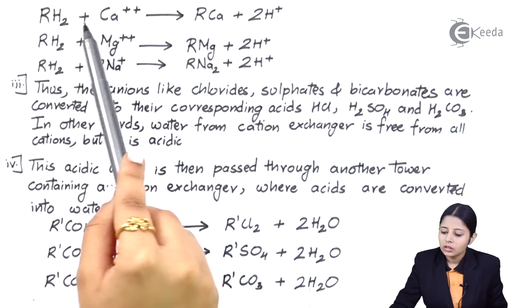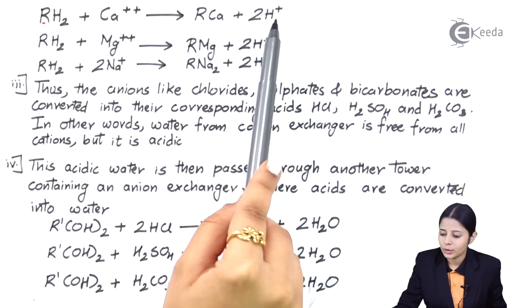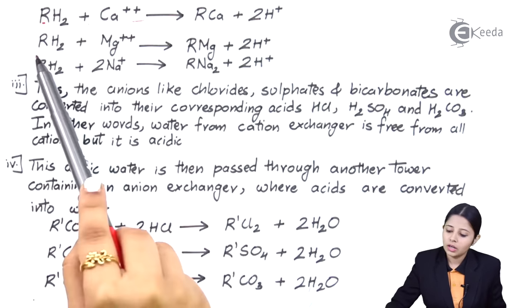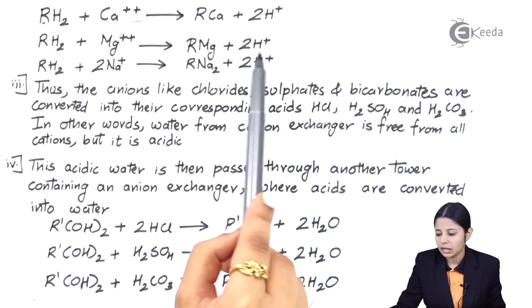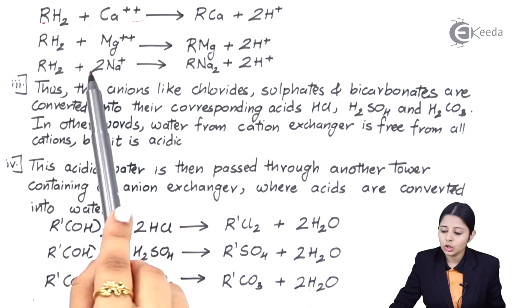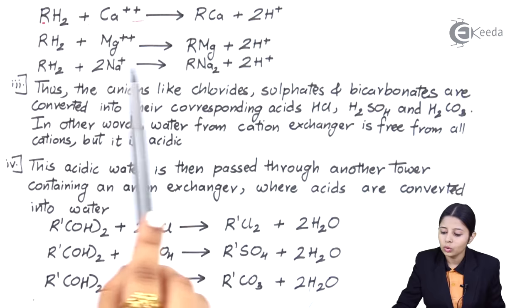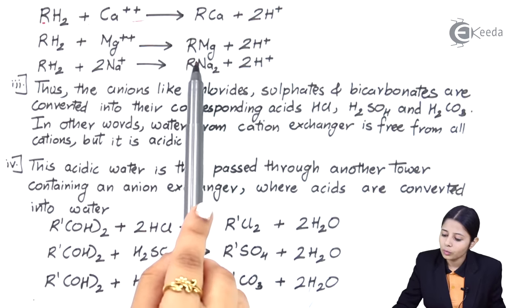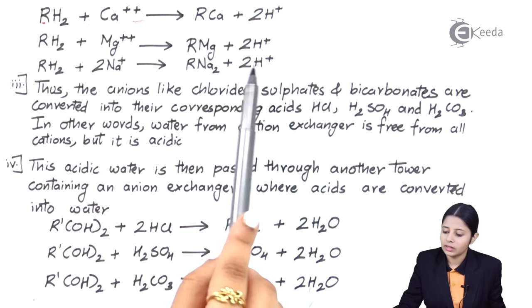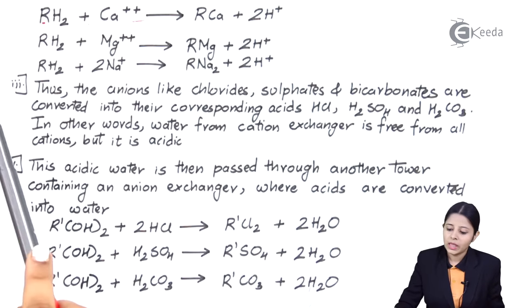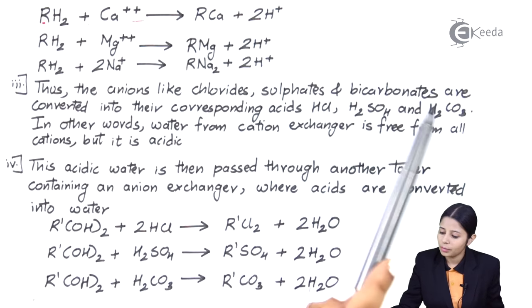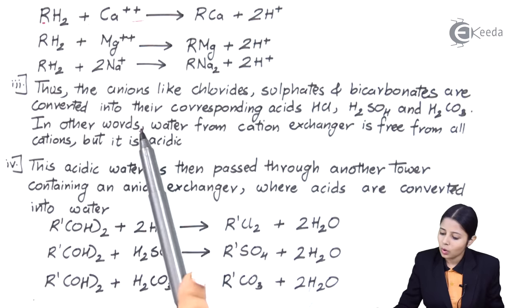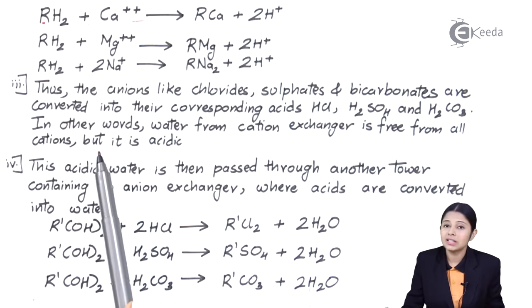The cation exchange reactions are: RH₂ + Ca²⁺ → RCa + 2H⁺; RH₂ + Mg²⁺ → RMg + 2H⁺; RH₂ + 2Na⁺ → RNa₂ + 2H⁺. So instead of Ca²⁺ or Mg²⁺ or Na⁺ ions, we now have only H⁺ ions. Thus anions like chlorides, sulfates, and bicarbonates are converted into their corresponding acids — HCl, H₂SO₄, and H₂CO₃. In other words, water from the cation exchanger is free from all cations but is still acidic.